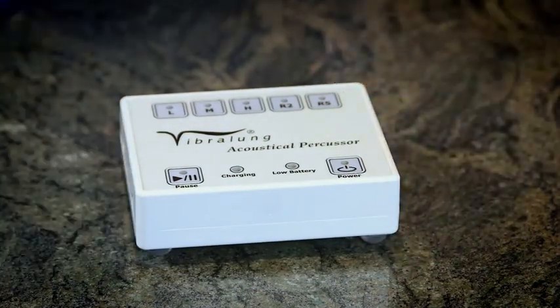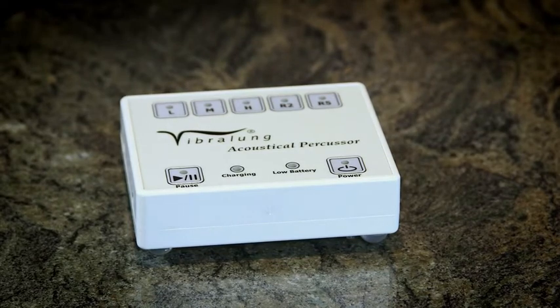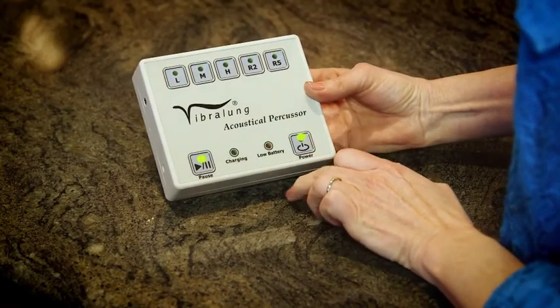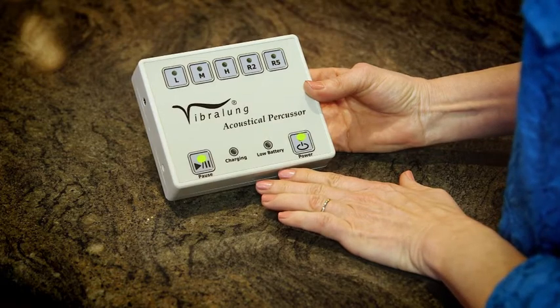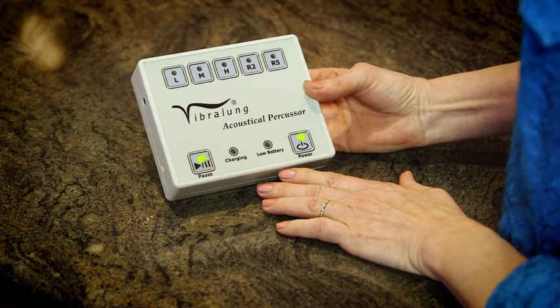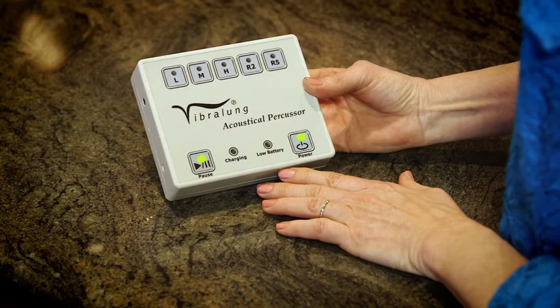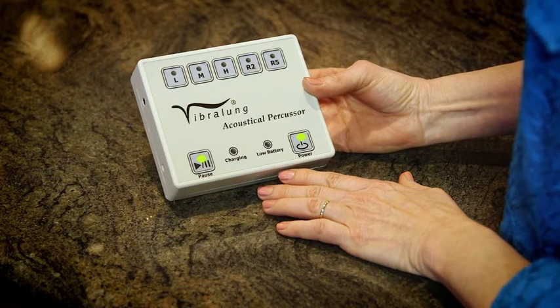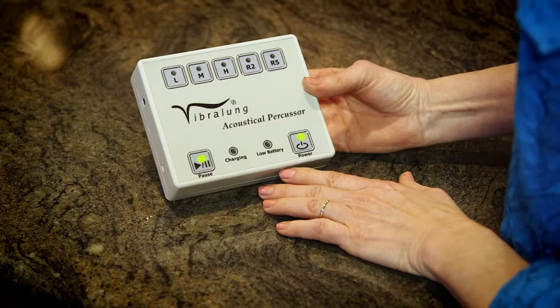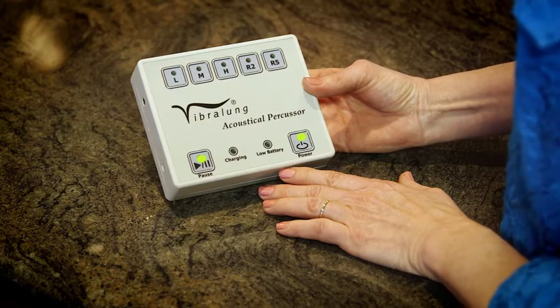Disconnect the battery charger after batteries are charged, as the treatment control unit will not operate while the charger is connected. Turn the treatment control unit on by pressing the power button once. The power on self-test will occur immediately as shown by all 9 LEDs on the treatment control unit flashing 3 times. The pause and power LEDs will remain illuminated. If other LEDs are illuminated, or if no LEDs are illuminated, the treatment control unit failed the power on self-test and should not be used. Contact WestMed customer service. The treatment control unit is now ready to use. Repeat these steps each time the treatment control unit needs to be recharged, as indicated by the low battery LED.